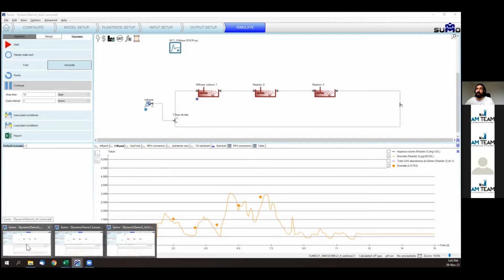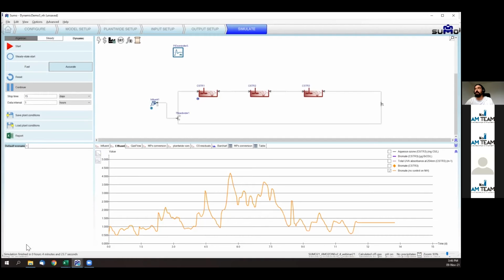But on the other hand, as we have been speaking about the ammonia, we can also have more fancy controllers and try to control bromate, optimizing the aeration at the upstream plant. So making sure there is a minimum ammonia concentration coming out, that we are not exceeding, of course, the effluent limits, but we can still have a sufficient action of ammonia on hypobromous acid. And that will result, as you can see from this purple line, in a shaving off of the peaks that I was talking about before. So in these cases, specifically at 4.5 days and 5.7 days, you can see that the peaks are shaved off just because we optimized the upstream wastewater treatment plant controller to ensure there was just enough ammonia to avoid the peak bromate formation.